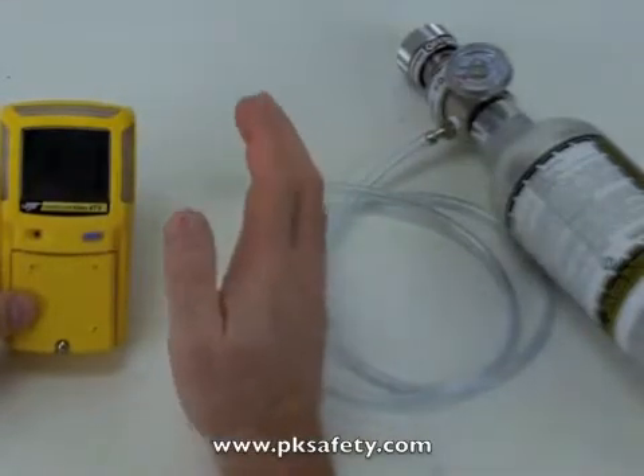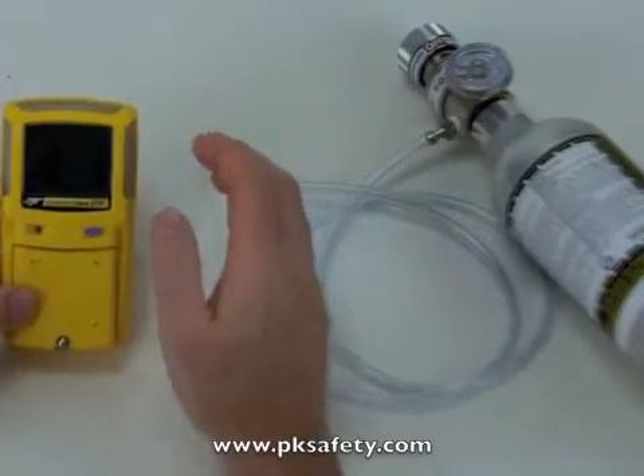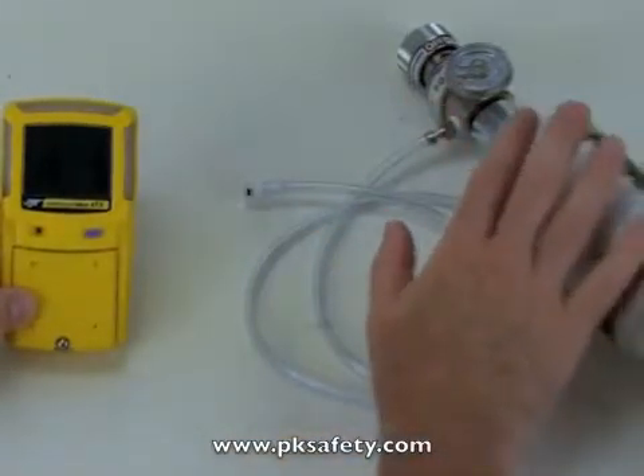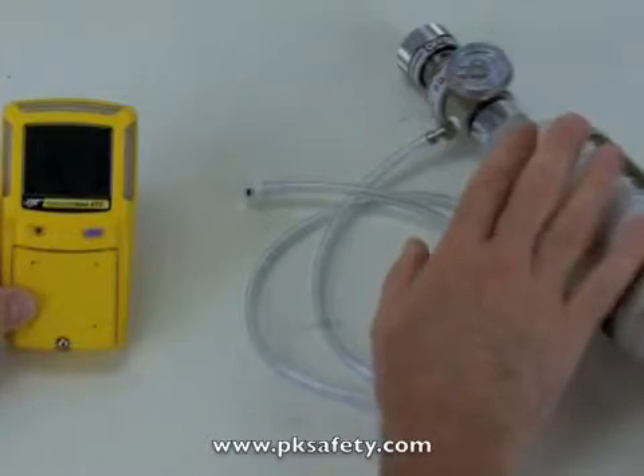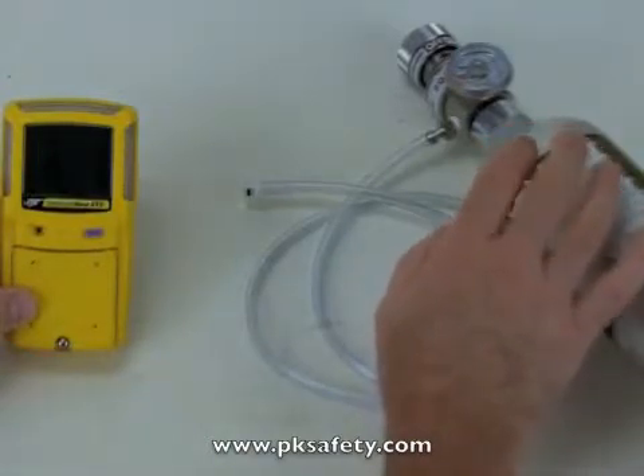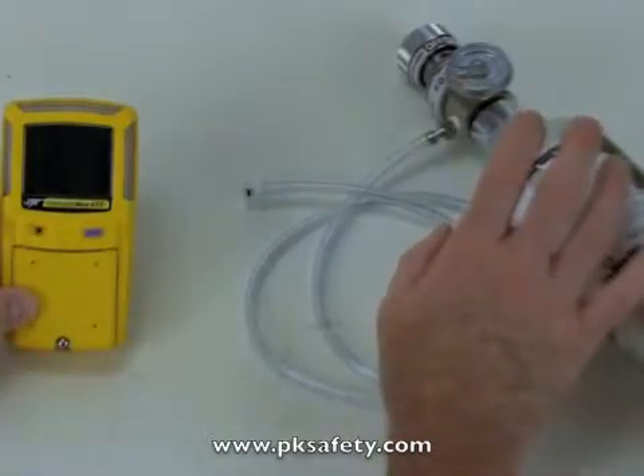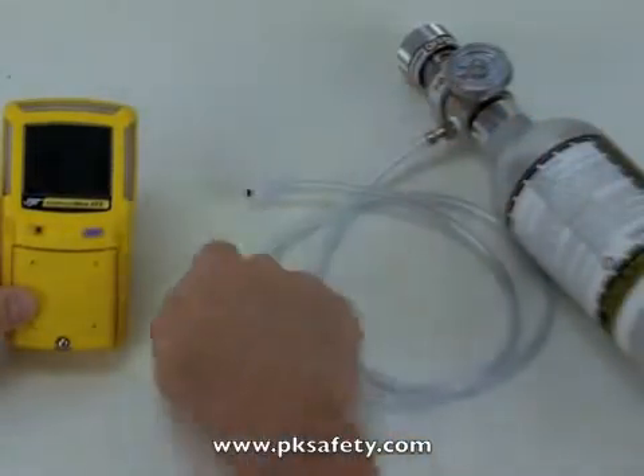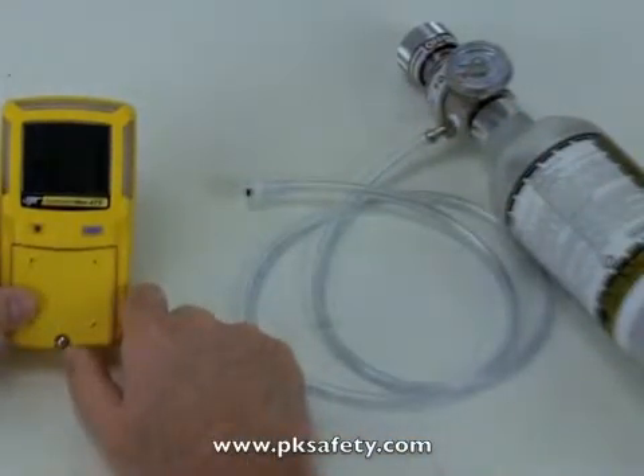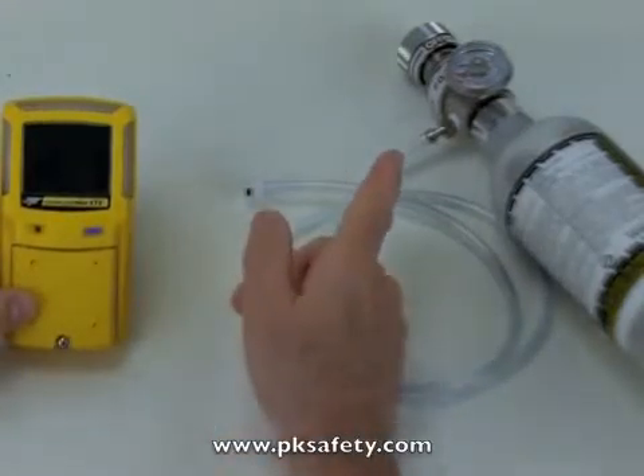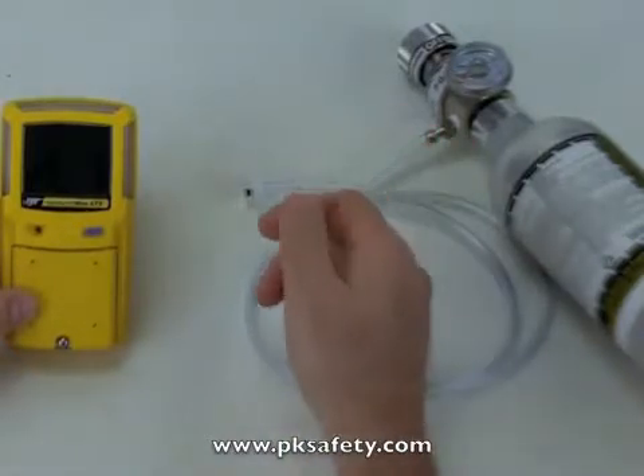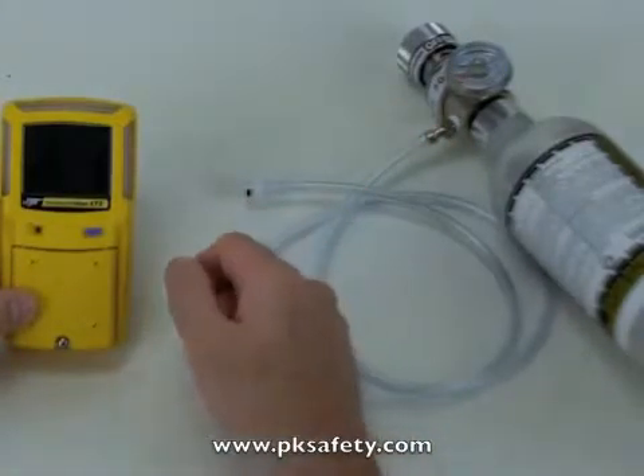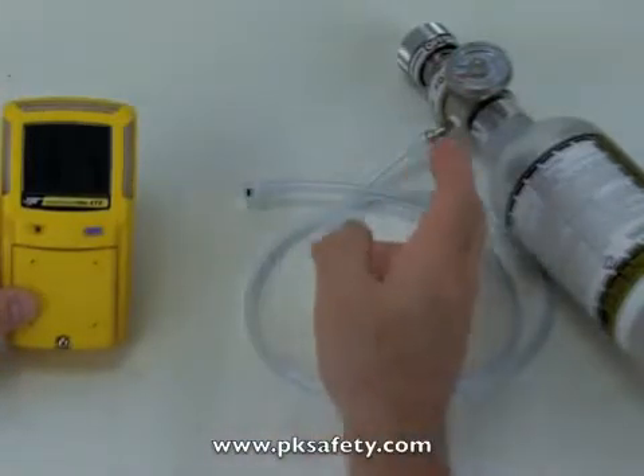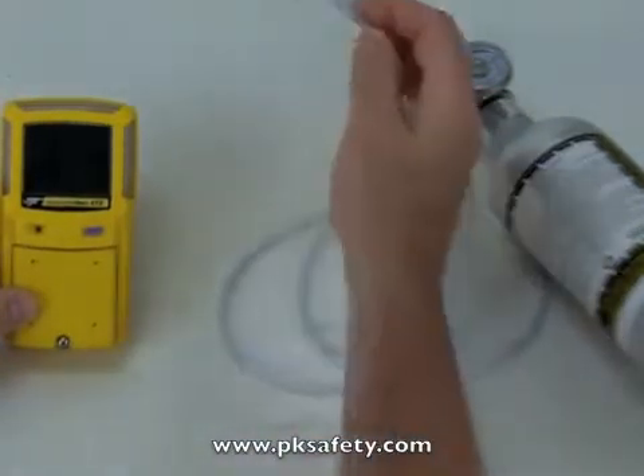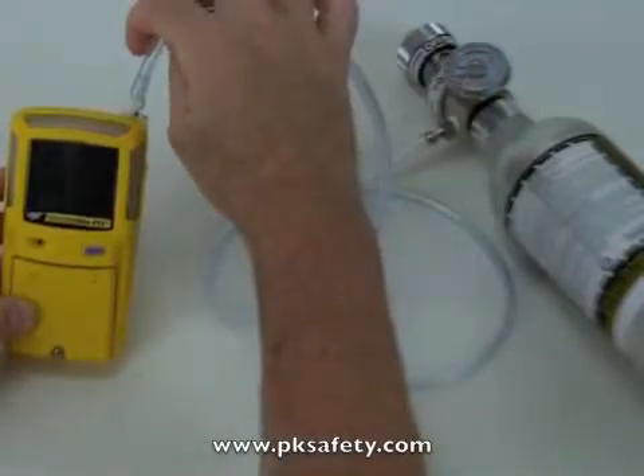And so what I'm going to do is introduce cal gas, and I'll kind of cover what we've got here. First, a cylinder of calibration gas. This has all four gases in it: the hydrogen sulfide, carbon monoxide, oxygen, and then the explosive gas, or LEL. On top, I have a regulator. Now this is a constant flow regulator, and it puts out a ½ liter per minute. This is the one that comes in the kit, and this one happens to be made by Portagas. BW does use other ones from time to time. But when we turn this on, it's going to flow the gas through this tube and out the end, which we're going to attach to the instrument.